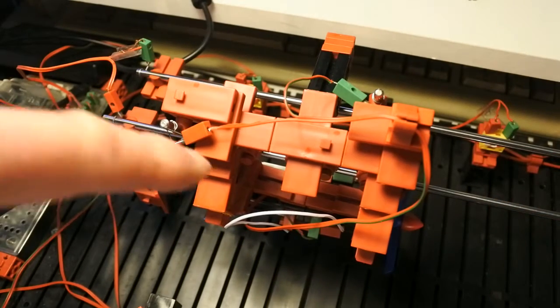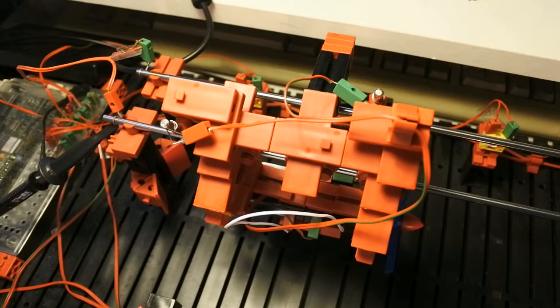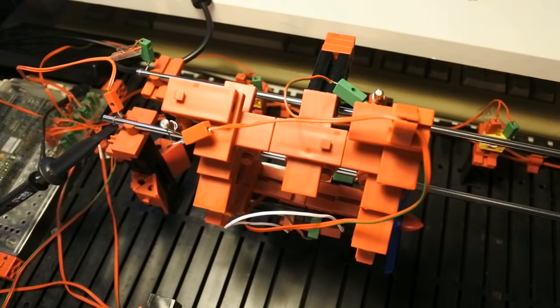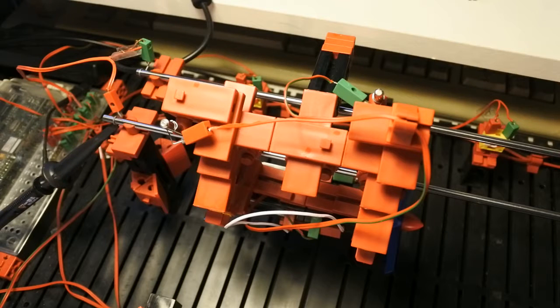The only point is now that it is going towards the controller, and that is never the intention. The intention is to go to the end of the track, and there's a good reason, because this one gives 1, 7 here gives 1, but at the end of the track it gives 0 again. So I have to use diagnostics to find out why.